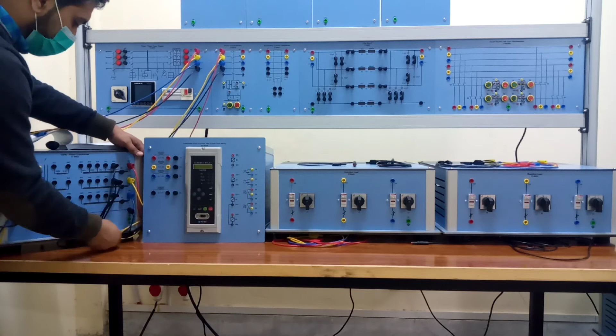This is the in, and you will take a direct out from here, not from the star point, but directly from this neutral at your three-phase transformer, and this will continue to the power circuit breaker. So this is the isolated neutral configuration for your system, and later on you will see the emphasis and the advantage of doing this.